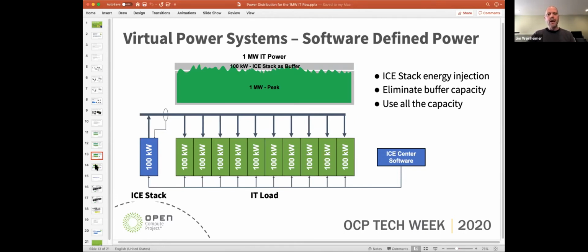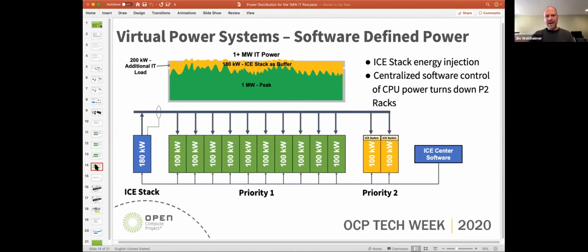On the next slide, we're layering in more software to control the racks that you've added in to drive up that average load when the demand for cat pictures isn't so high. So when the demand on the primary systems is high and it's reaching the peak power draw, the energy storage systems can help to limit the load seen at the upstream systems. But eventually those energy storage systems will be depleted and the load will need to be shed to maintain the SLAs on that priority one equipment.